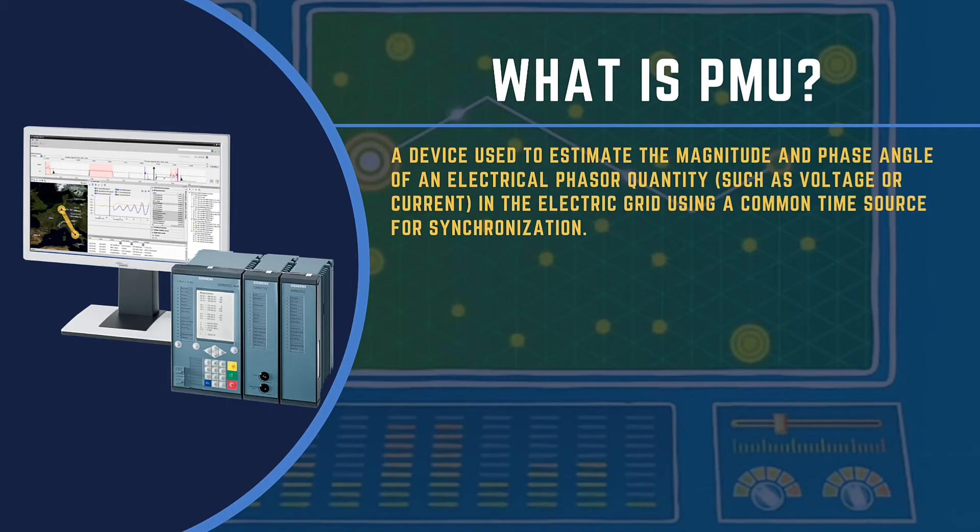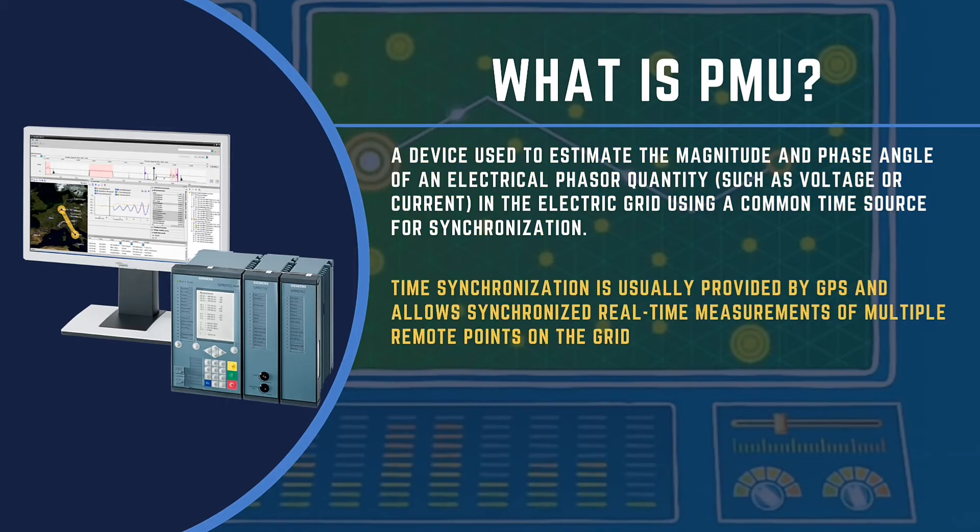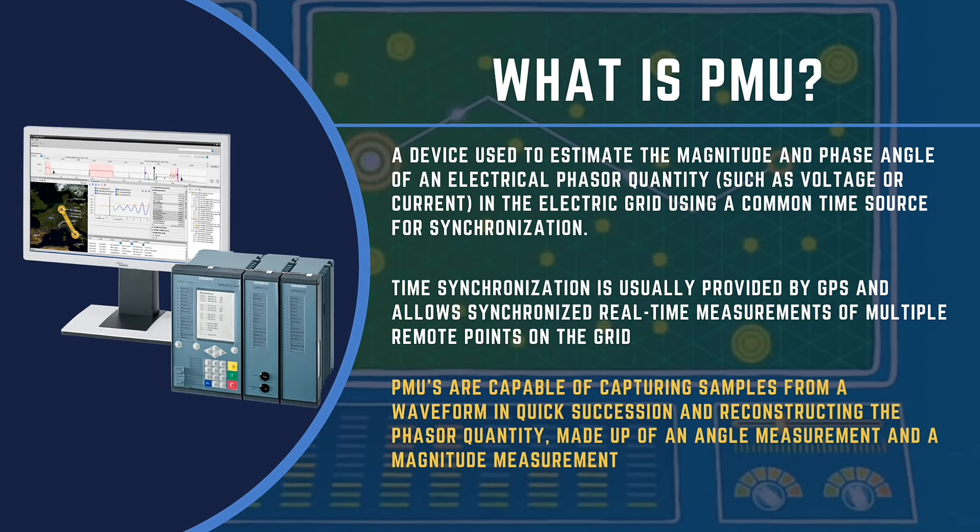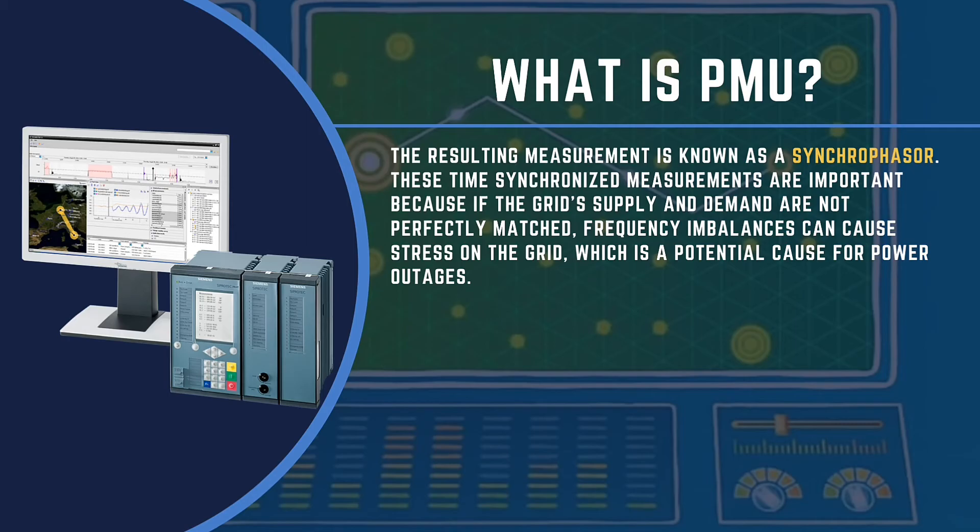A phasor measurement unit is a device used to estimate the magnitude and phase angle of an electrical phasor quantity, such as voltage or current, in the electric grid using a common time source for synchronization. Time synchronization is usually provided by GPS and allows synchronized real-time measurements of multiple remote points on the grid. Phasor measurement units are capable of capturing samples from a waveform in quick succession and reconstructing the phasor quantity, made up of an angle measurement and a magnitude measurement. The resulting measurement is known as a synchrophasor.